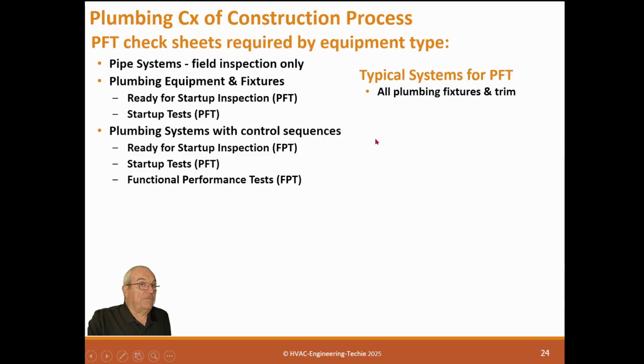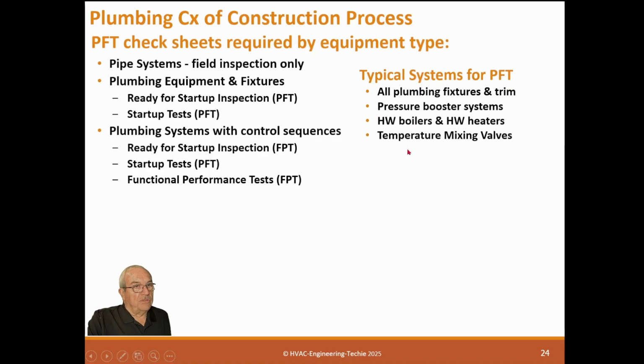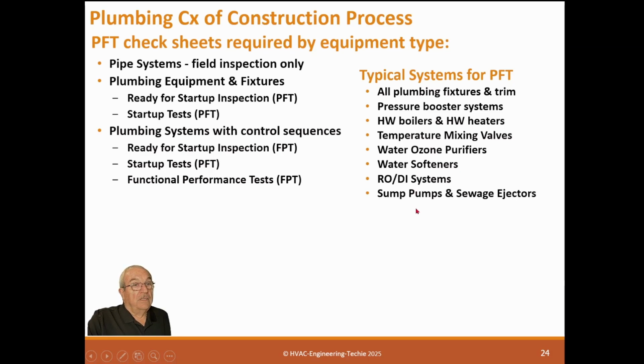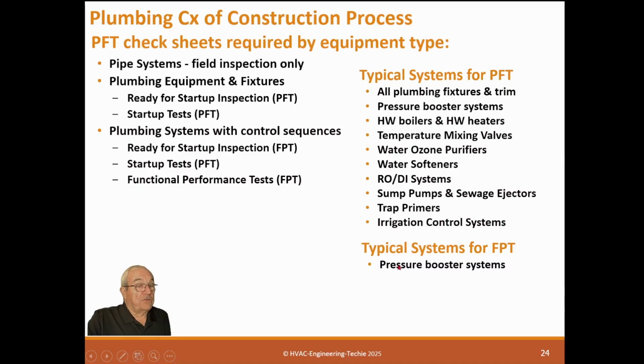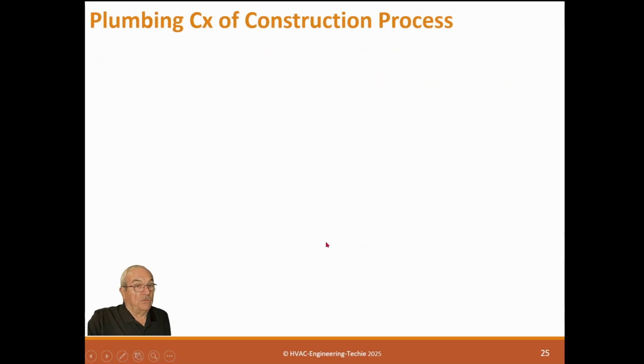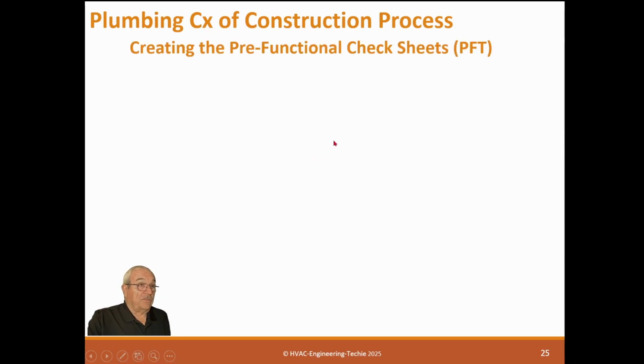Typical systems for PFTs are all plumbing fixtures and trim, pressure booster systems, hot water boilers and heaters, temperature mixing valves, water ozone purifiers, water softeners, RODI systems, sump pumps and sewage ejectors, trap primers, irrigation controllers and systems. Typical systems for FPT: pressure booster systems, touchless faucets and flush valves, hot water temperature control devices. So you can see there's not many functional tests. That's why plumbing systems are much easier than HVAC systems, which have a lot of functional tests.